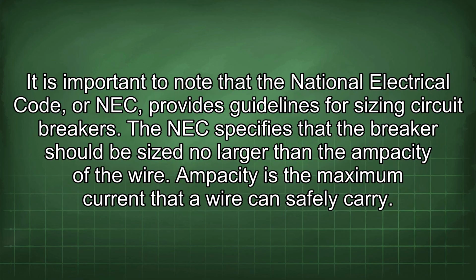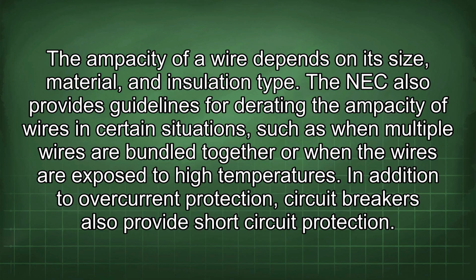It is important to note that the National Electrical Code, or NEC, provides guidelines for sizing circuit breakers. The NEC specifies that the breaker should be sized no larger than the ampacity of the wire. Ampacity is the maximum current that a wire can safely carry. The ampacity of a wire depends on its size, material, and insulation type. The NEC also provides guidelines for derating the ampacity of wires in certain situations, such as when multiple wires are bundled together or when the wires are exposed to high temperatures.